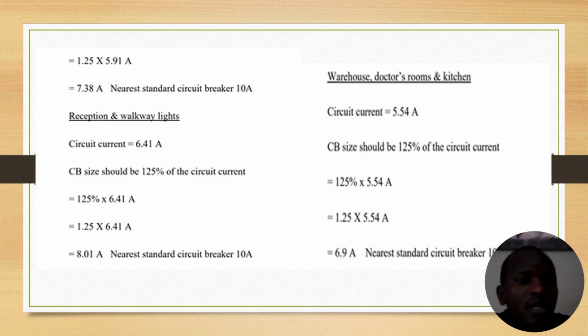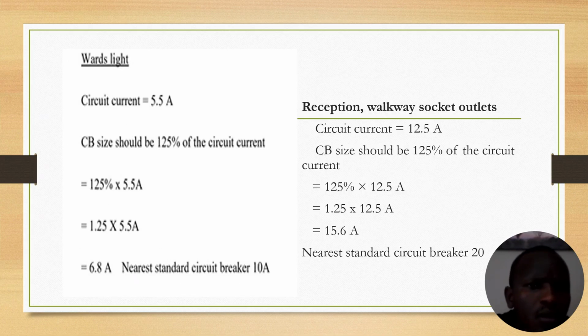Then as you can see, the reception size is 6.41, we will take 10 amps. On the warehouse for the doctor's room and kitchen, it will also take 6.9 amps. The 6.9 amps is then converted to 10 amps, so we are going to have 10 amps for the lights. This is the calculation for the reception walkway socket outlets, where the nearest standard will be 20 amps because it's 15.6 amps.